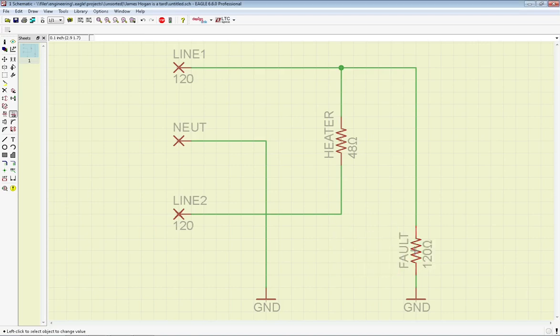But there isn't a situation mathematically where you get 120 volts across that heater, unless, put that thermostat back there, the only way you get 120 volts across this heater is if this end is at 120 and this end is at 0, because that gives you a difference of 120. Any other number, any resistance here, any resistance right here, is going to cause the voltage here to go up, because you have a voltage divider through this, this, this, this, and this. Plain and simple. It's a voltage divider.